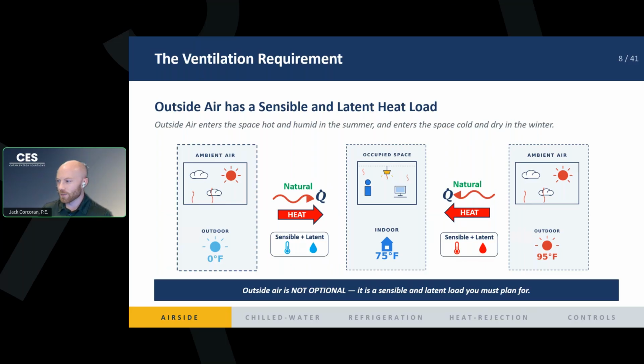Now, the flip side is also true. If it's a really hot summer day, you're bringing in a lot of hot and humid outside air into your 75-degree space, which we don't really want to do. Otherwise, in both situations, our indoor air is not going to be very comfortable for our occupants. So we need to make sure we account and plan for this sensible and latent load that we're adding into our space.